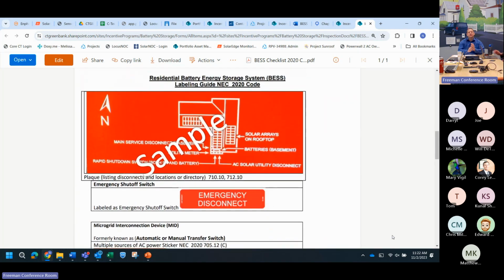The beauty of this checklist is that it shows what the stickers look like. This is a plaque—you'll need at least two, maybe three. Usually a plaque is required at the meter outside, at the main panel, and usually at your hub. Not all systems have a hub, but if you have one, you probably need a plaque there too. This is a sample I took a picture of from an installer, because it's simple and not loaded down with junk.